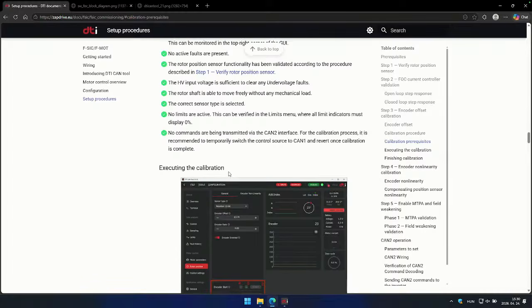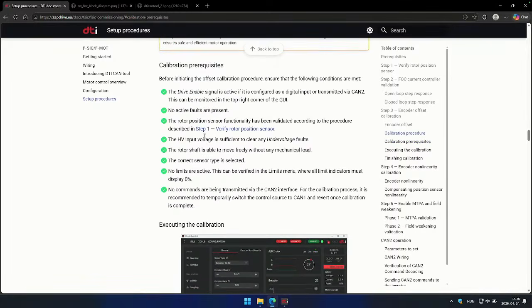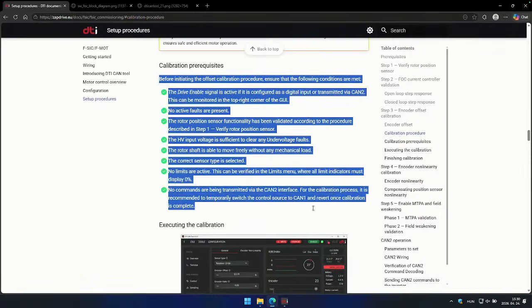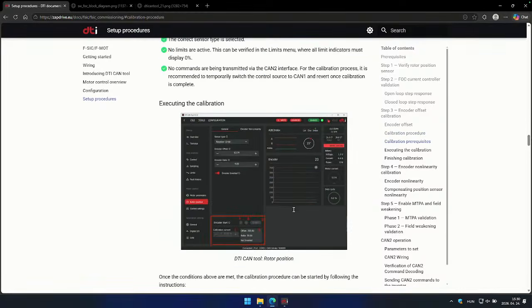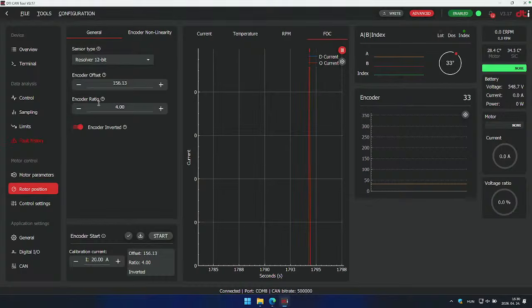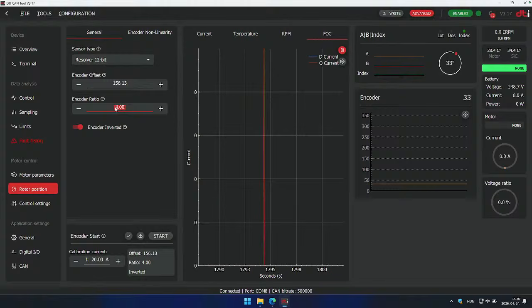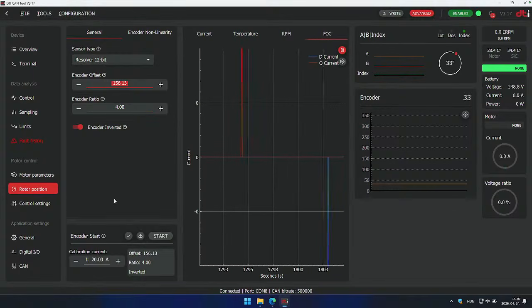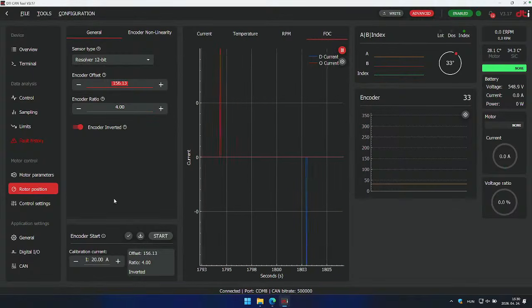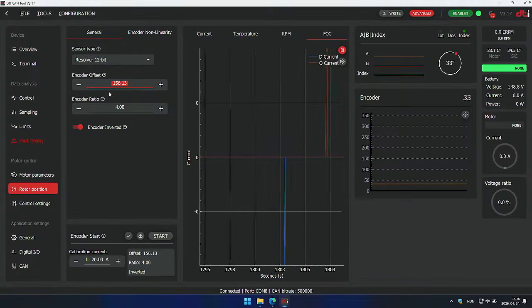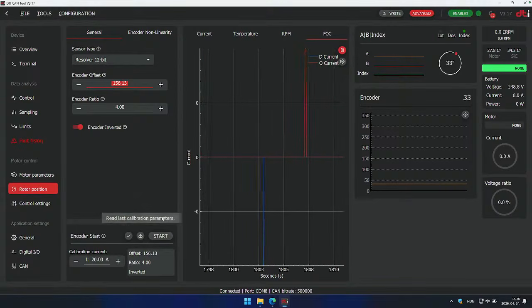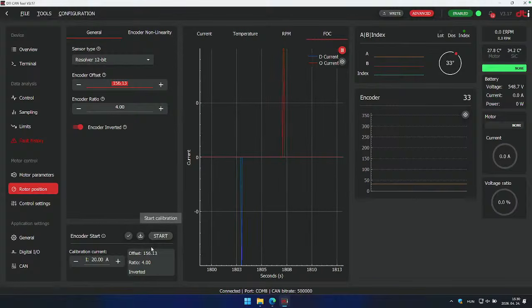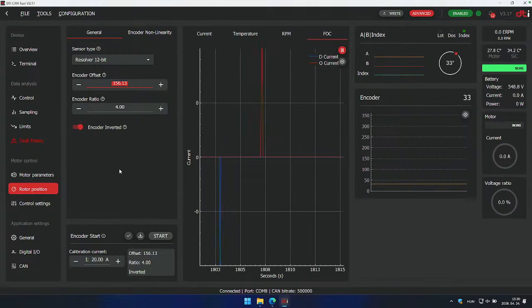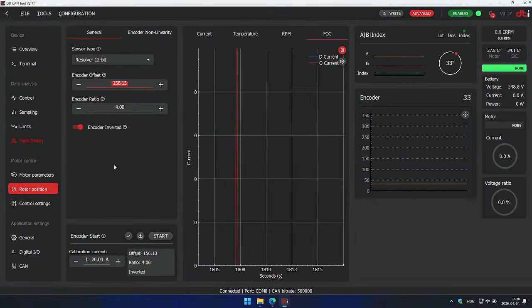We know that the current control works fine. Also, there are calibration prerequisites before the encoder calibration. And the encoder ratio is 4. This motor has 4 poles, so it's quite good. This number cannot be validated, basically. You can just make sure that if you execute it 3 or 4 times, you get the same value, and the encoder inverted is also a given value.